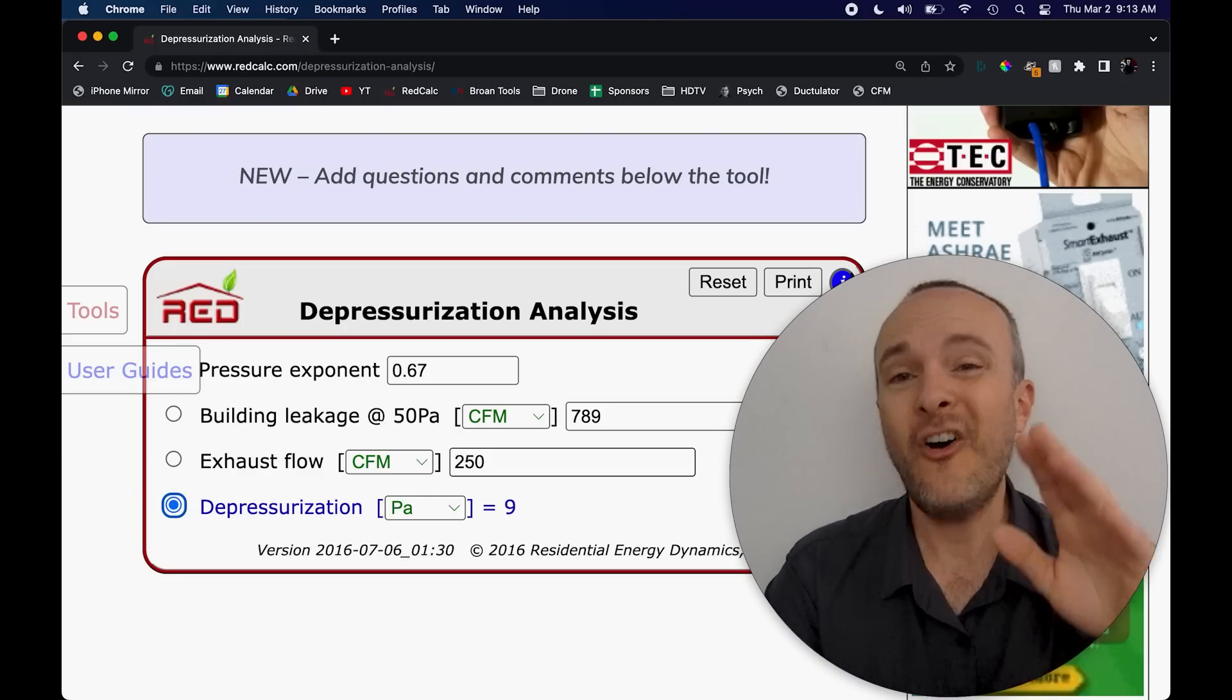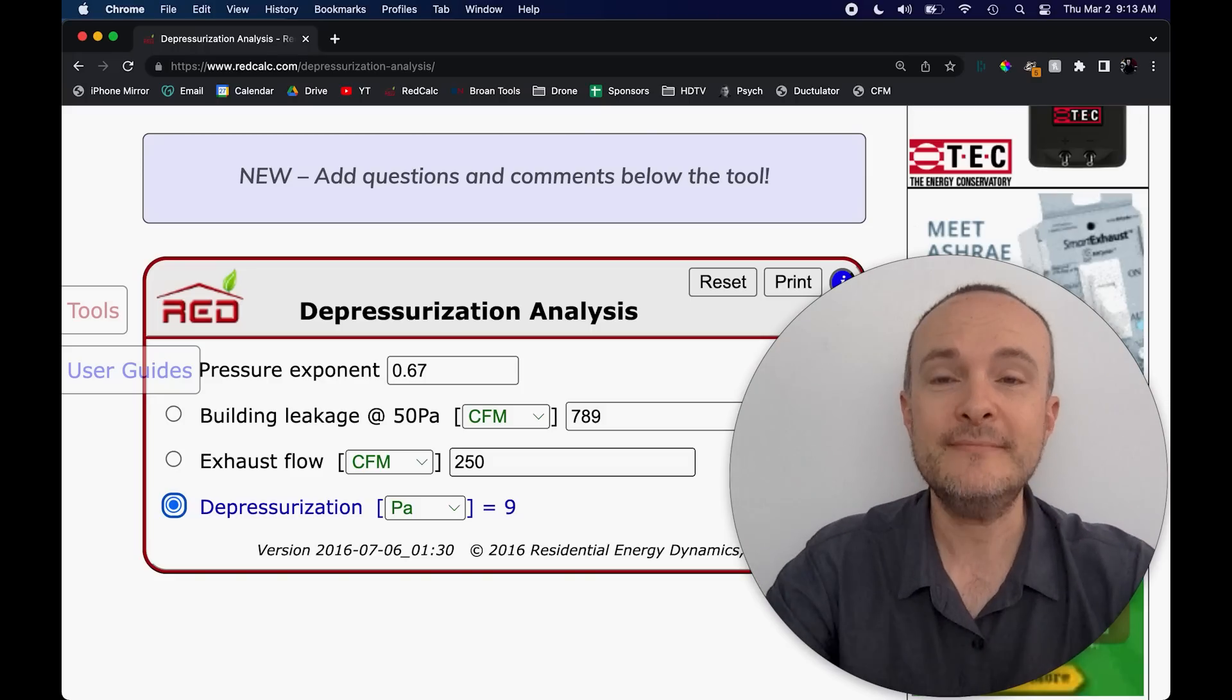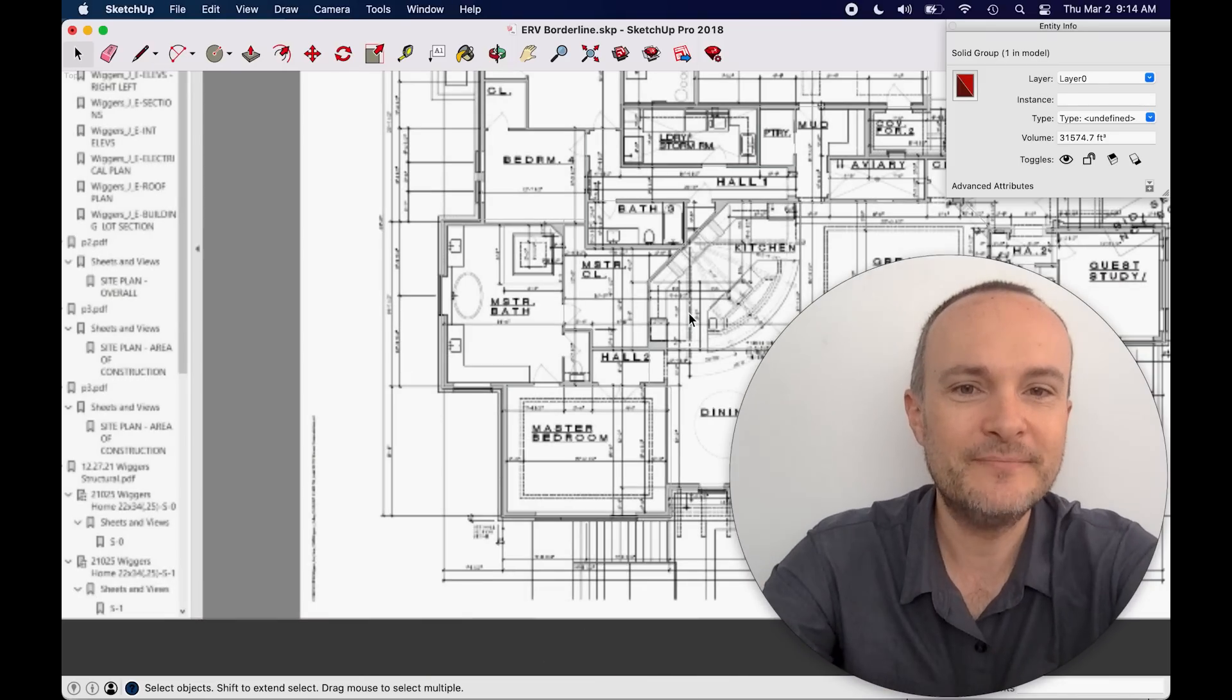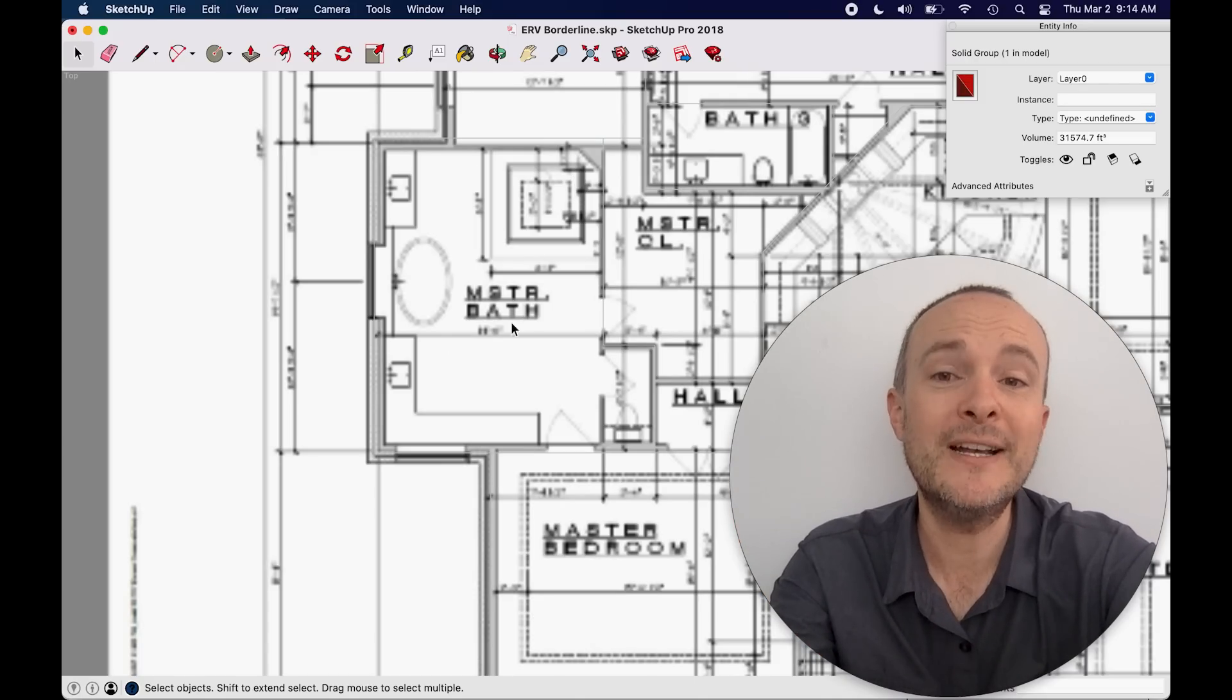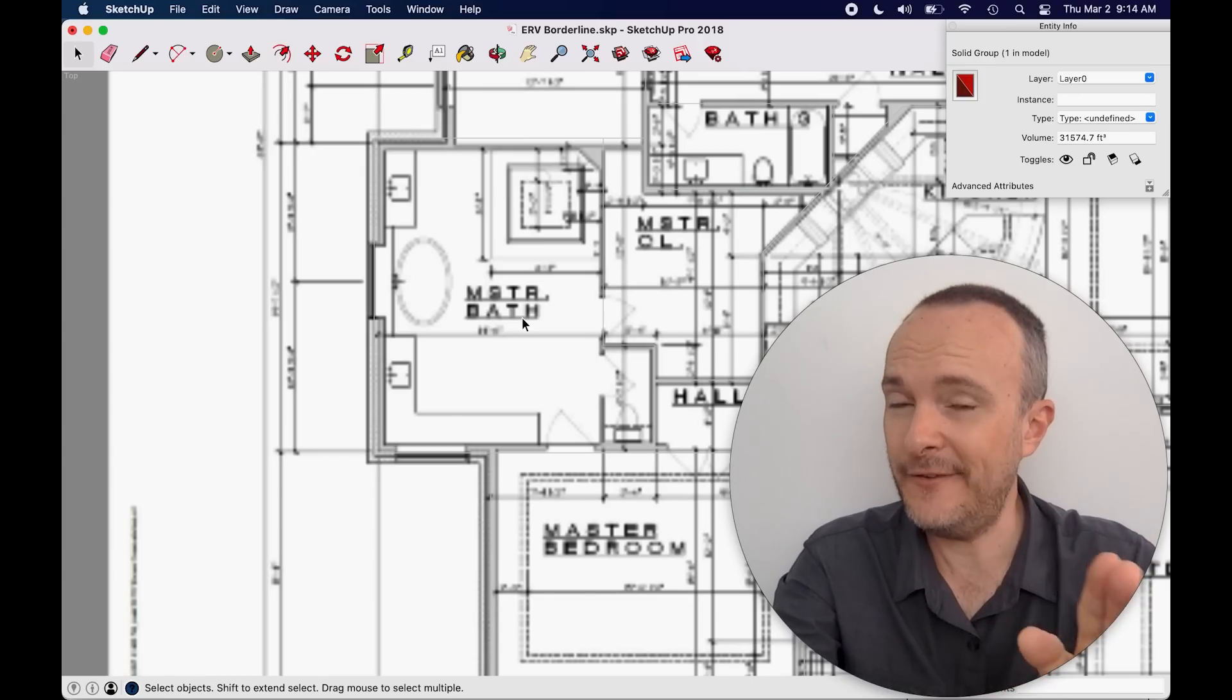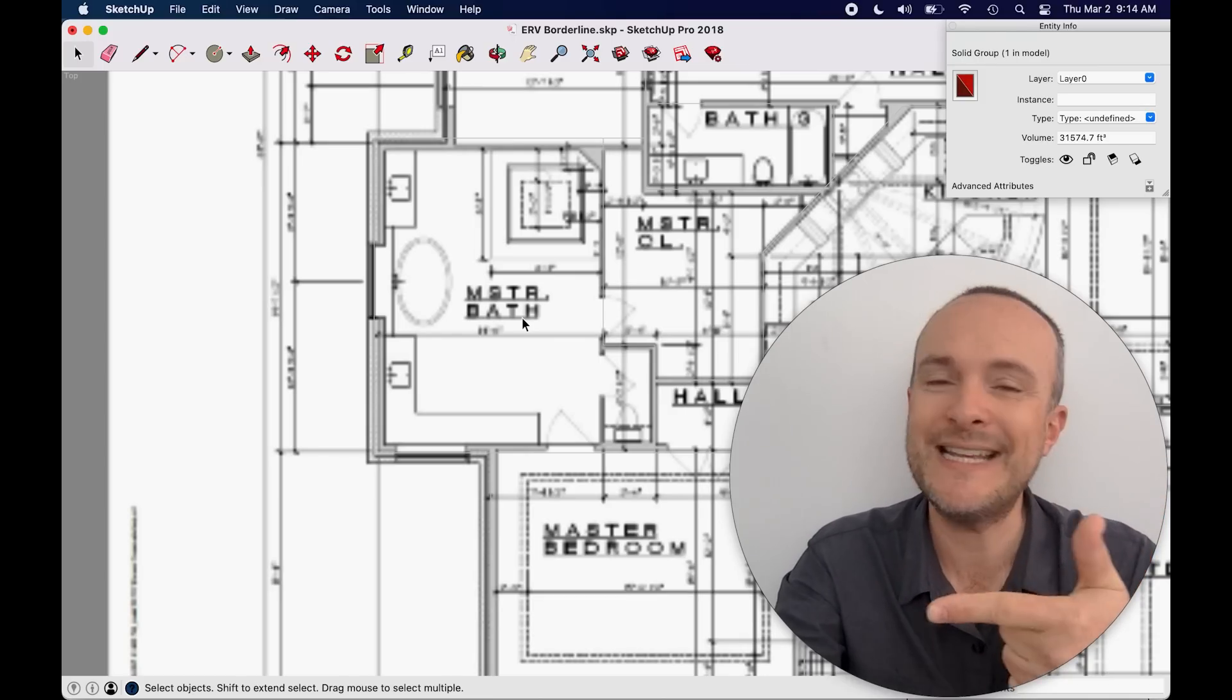Also, let's be honest, builders are not using 50 CFM exhaust fans generally. They're going to be putting, instead of looking at the, let me go back to my 3D model here. So if you were going to put your exhaust fan in the master, right, we got this big old master here. They're not going to put the exhaust fan in the shower where it belongs. They're going to put it in the middle of the room. And now what they're going to do is install an 80 CFM or 110 CFM or 150 CFM exhaust fan, because number one, it's not going to be in the right place. So it's not going to work as well. So they need more fan power.